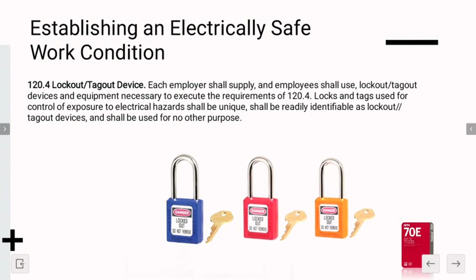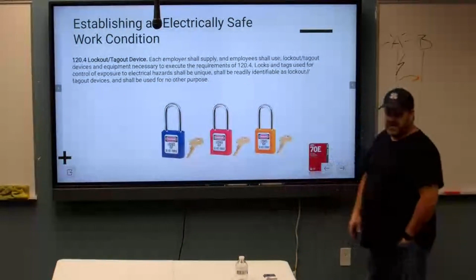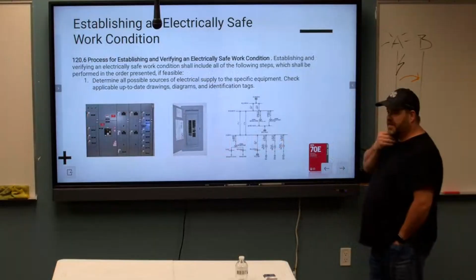Real quick, our lockout devices. The 70E says that the employer has to supply the lockout devices and they have to be readily identifiable as a lockout device, and they can't be used for any other purposes. So you should be able to look at a lock and know that somebody locked out a circuit or source of hazardous energy. You should be able to know that that's the case and that lock isn't secured. Does that make sense? And you can't use them for any other purpose, okay? So you can't lock your pack outs with them or your wave runners at home or whatever.